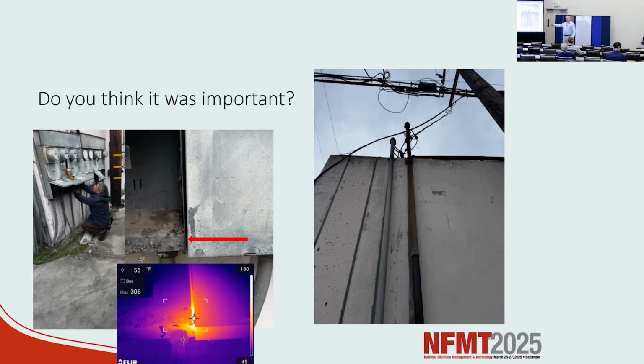Can anybody read that temperature on the bottom there? This is his main panels outside, with 11 panels coming in, meters. This is a meter section that's 306 degrees. When I opened up the circuit, the electrician opened it up, there were no wires there. What was happening was the feeders were causing a fault, there was probably a nick in the feeder insulation, and it was electrifying the box. Because the boxes are grounded, it was carrying and completing a circuit, creating a 306 degree fault.